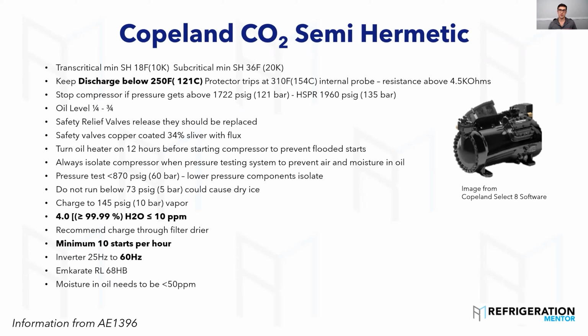Different viscosity. Moisture in oil needs to be less than 50 parts per million. So this is, once again, talking a lot about moisture in the systems, but I've seen a ton of it as seeing and opening up hundreds and hundreds of compressors, doing trainings all over the place. There's moisture in too many systems out there. So make sure, especially with CO2, you get that moisture out. Here was another difference. I didn't bold this one, but Copeland recommends evacuating down to 225 microns, 0.3 mbar. 1 millibar equals 750 microns. So that's even lower than what Bitzer says.